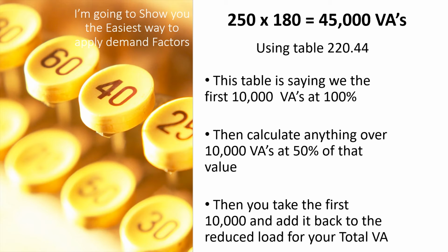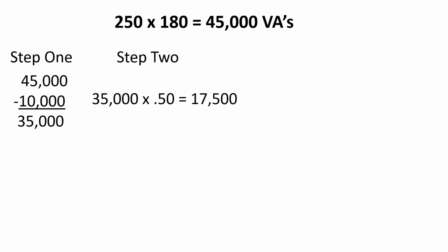Okay, so that was our total VAs. In step 1, you take your total VAs and subtract the 10,000 that you must calculate at 100%, so we set it to the side. That leaves us the 35,000 remaining. Now we must multiply that by 0.50, the demand factor, and that is going to give us 17,500.